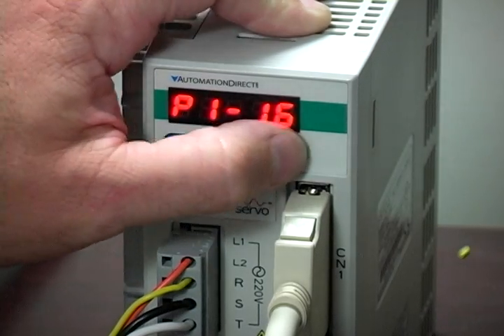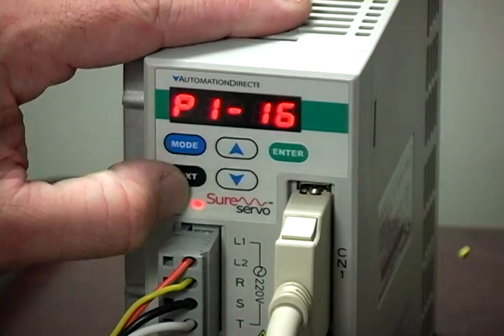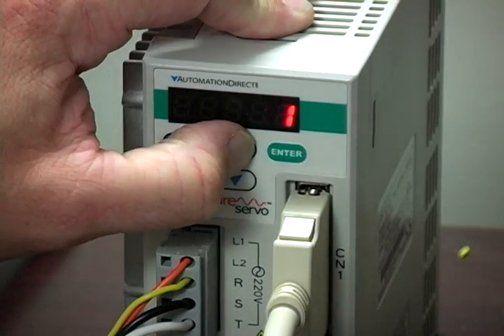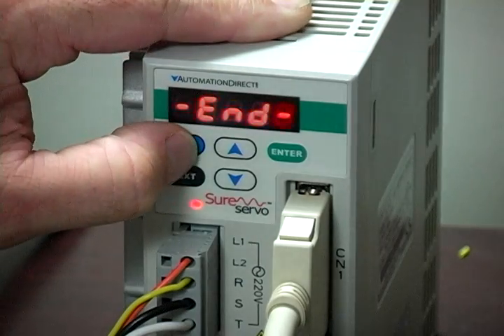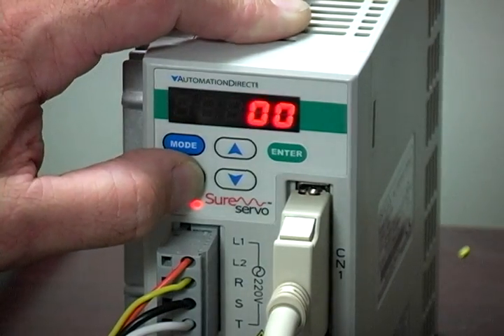Let's set position 2 to exactly 3 and 1 half revolutions. Set P1-17 to 3 and because one motor revolution consists of 10,000 encoder counts, set P1-18 to 5,000 to achieve one half a revolution.